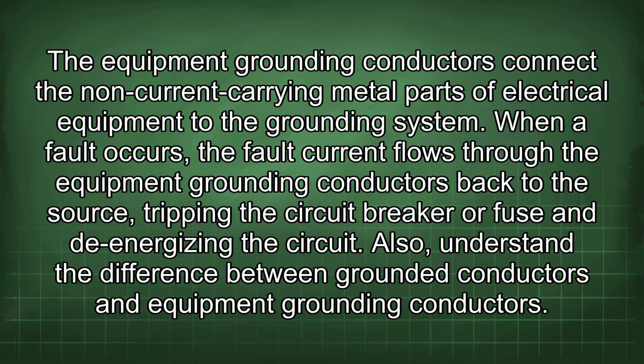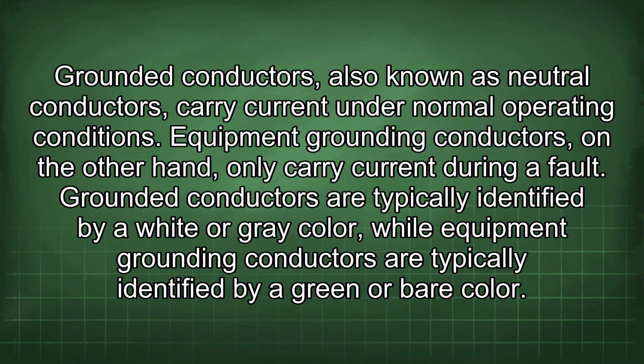When a fault occurs, a fault current flows through the equipment grounding conductors back to the source, tripping the circuit breaker or fuse and de-energizing the circuit. Also, understand the difference between grounded conductors and equipment grounding conductors. Grounded conductors, also known as neutral conductors, carry current under normal operating conditions. Equipment grounding conductors, on the other hand, only carry current during a fault.